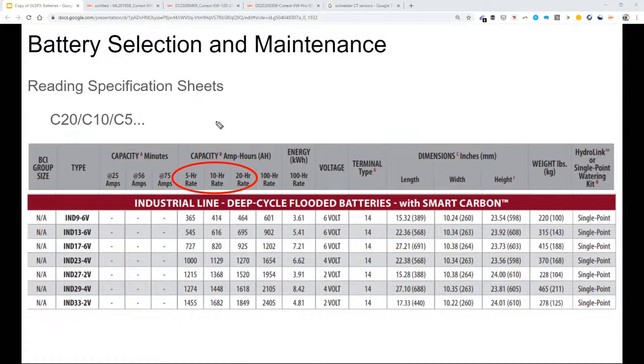But if you look at a lead acid battery spec sheet, you'll get different amounts of storage capacity for if it's discharged over a 20-hour period, or over a 10-hour period, or over a 5-hour period. You'll get this many total amp hours out of it at its voltage. So what you're seeing is the kilowatt hour storage capacity of the battery is decreasing as the discharge rate increases. So the faster you discharge a lead acid battery, the less capacity it has in it.